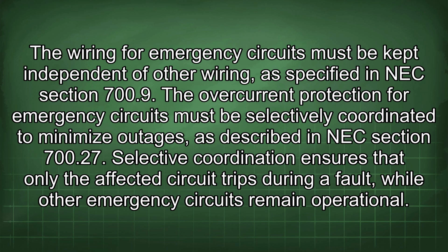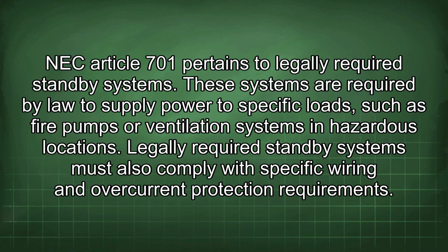The overcurrent protection for emergency circuits must be selectively coordinated to minimize outages, as described in NEC section 700.27. Selective coordination ensures that only the affected circuit trips during a fault, while other emergency circuits remain operational. NEC Article 701 pertains to legally required standby systems. These systems are required by law to supply power to specific loads, such as fire pumps or ventilation systems in hazardous locations.